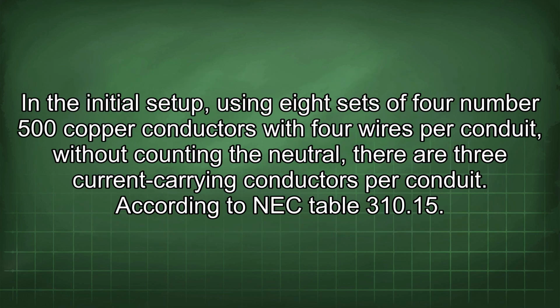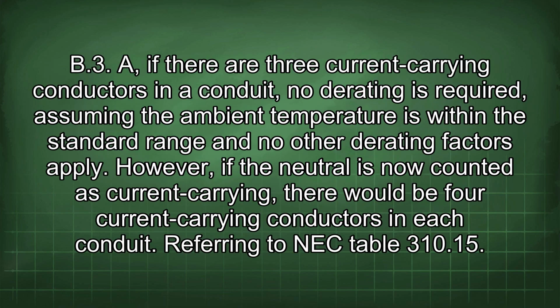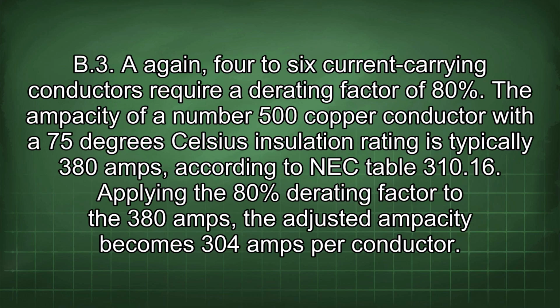In the initial setup, using 8 sets of 4 number 500 copper conductors with 4 wires per conduit, without counting the neutral, there are 3 current carrying conductors per conduit. According to NEC table 310.15(B)(3)(a), if there are 3 current carrying conductors in a conduit, no derating is required, assuming the ambient temperature is within the standard range and no other derating factors apply. However, if the neutral is now counted as current carrying, there would be 4 current carrying conductors in each conduit. Referring to NEC table 310.15(B)(3) again, 4 to 6 current carrying conductors require a derating factor of 80%.